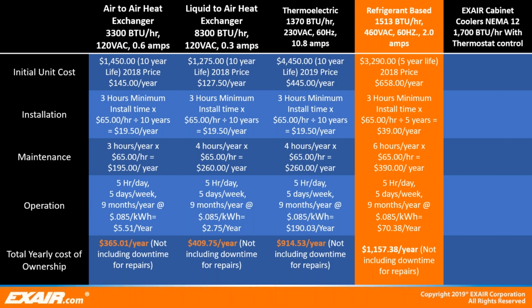We calculate that off of running watts, 5 hours a day, 5 days a week, 9 months a year, at 8.5 cents per kilowatt hour, and we come up with a value of $70.38 a year. The total cost of ownership per year comes in at $1,157.38 a year, not including downtime and production for repairs.